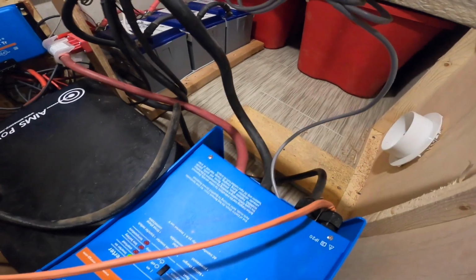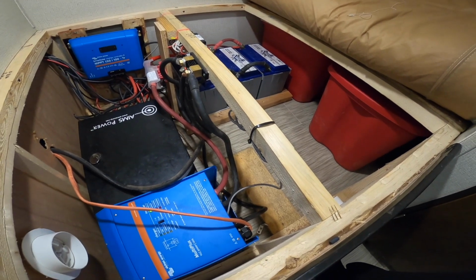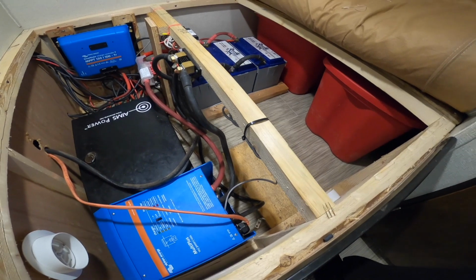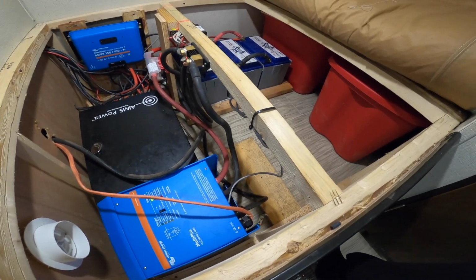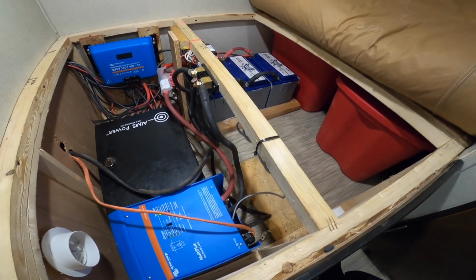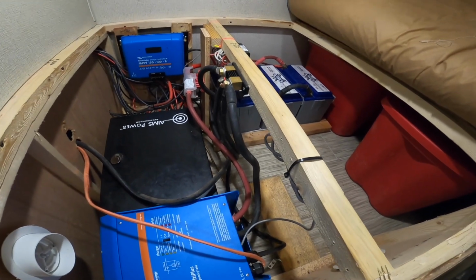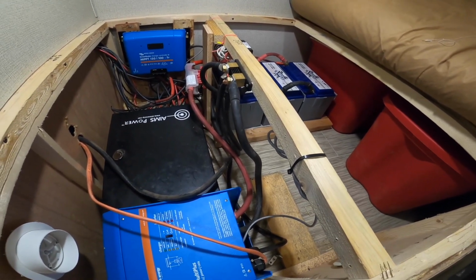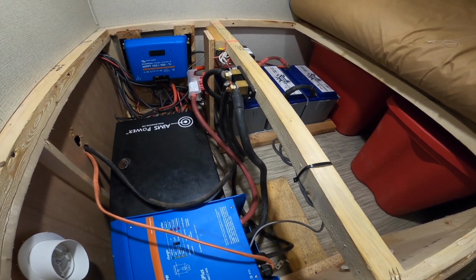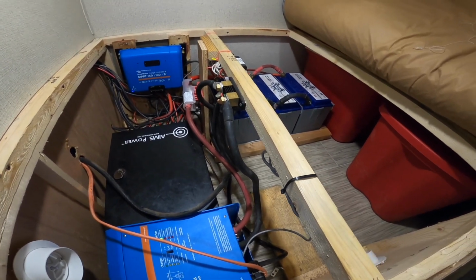We went with 4-aught cable into this inverter. So when I first set this system up, we had a question of whether that could get in there, and we did 2 smaller wires into that inverter, but we figured out that you could take 4-aught cable into the inverter, which makes it a more powerful system, the bigger cable, and it is a welding wire cable. Originally I had set this up with regular house wire. I think it's called THHN something. Anyway, it's got like 7 strands inside of it, and it's a big wire.